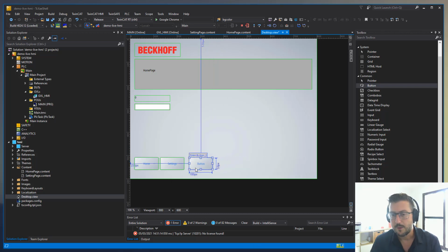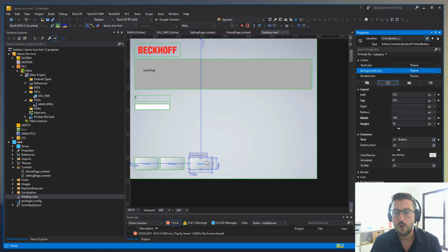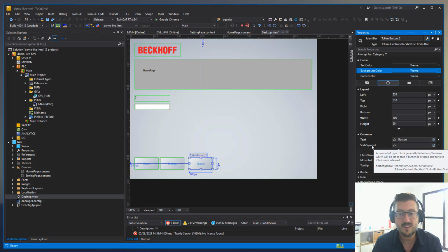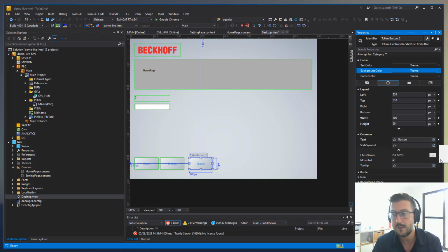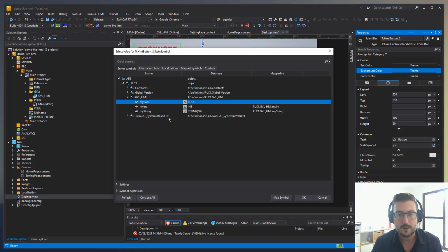And this button here, we could do on press, set a symbol, and on release, set a symbol to false. So we can do true and false on the on events. But some controls as well have things like state symbol. So just to make your life slightly easier, not create functional binding, which I will discuss in a moment, create a data binding into myBool.